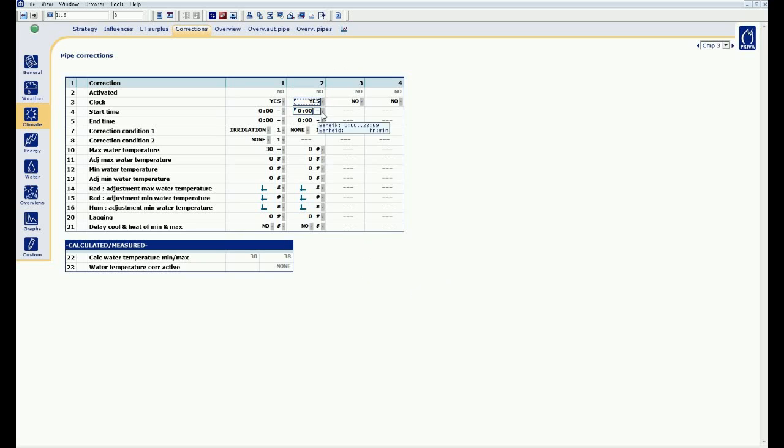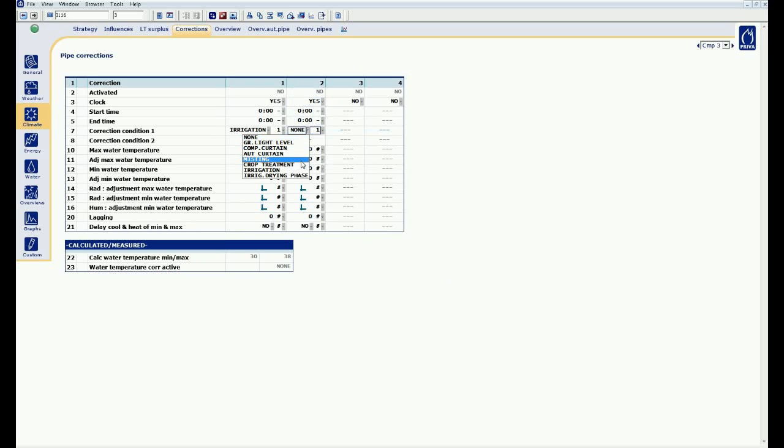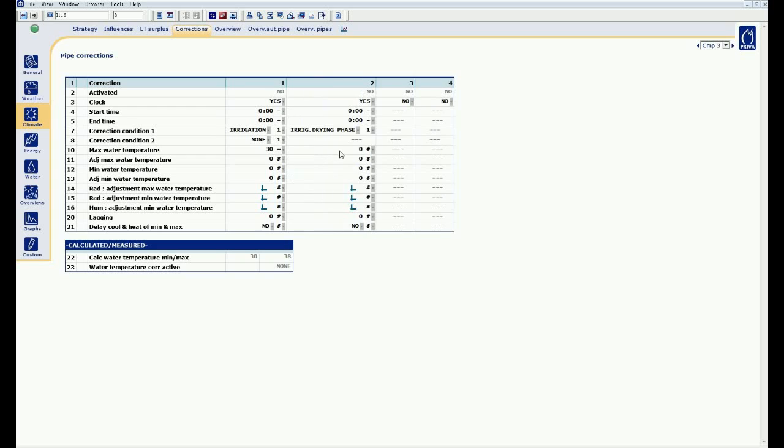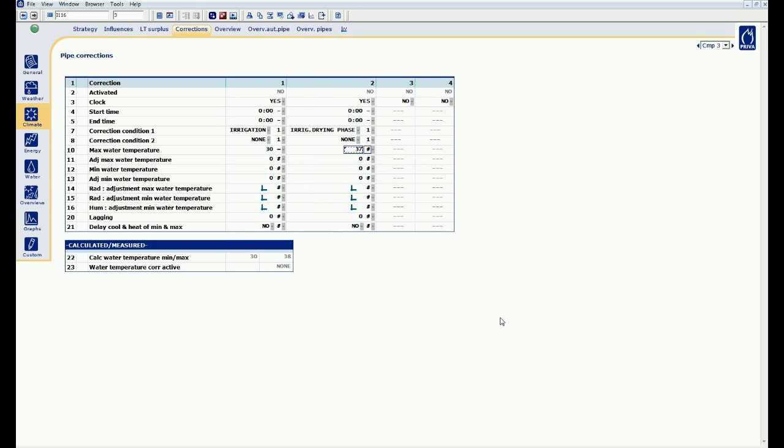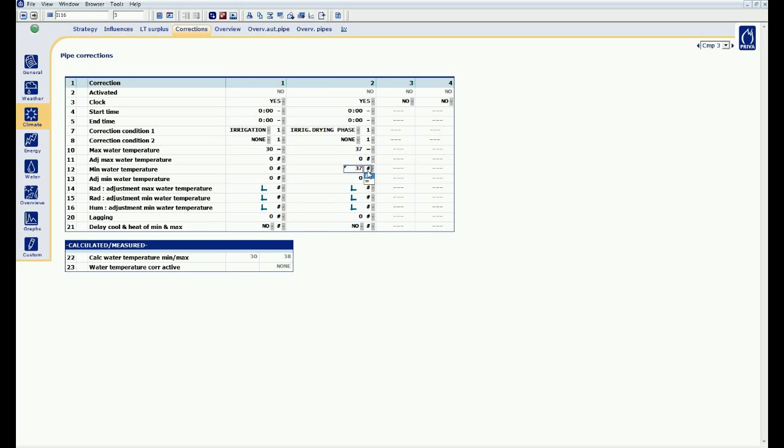The second period. I am going to use this for drying the crop. I use the drying phase 1, and during drying I want to have a maximum pipe of 37 degrees. With the equal sign, I take over the value, and I also set the minimum pipe temperature at 37 degrees. So during drying phase 1, the pipe temperature is fixed at 37 degrees.